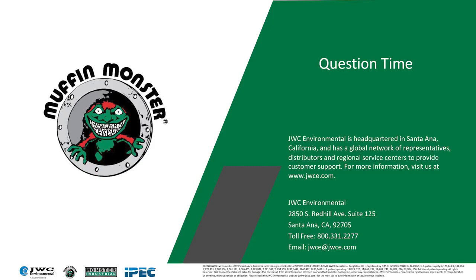That's a good question. You can definitely use multi-rake screens in septage receiving. Really, the thing with septage is to keep it moving. So adjusting the rise and run in an incoming channel in front of a multi-rake is going to be important. And you can add water in the septage process to keep it moving, and it really helps to do so. So those are probably two things I would suggest when using a multi-rake: don't be afraid to add water in front of it to keep it moving and make sure that all your solids get into the multi-rake.